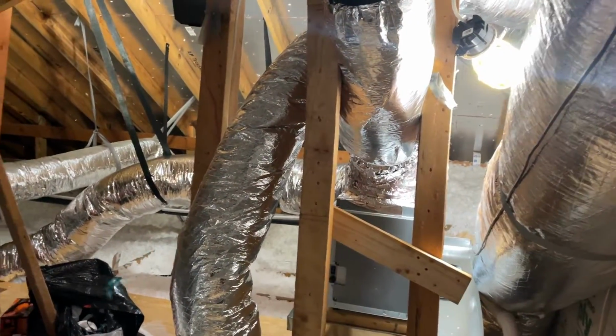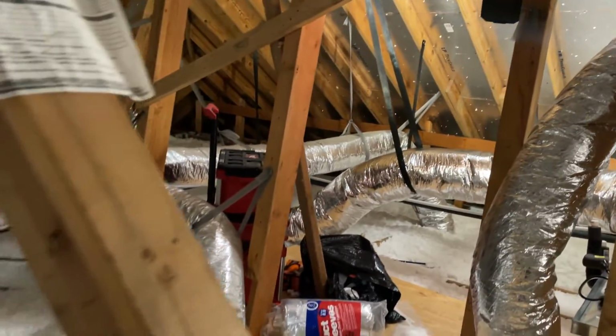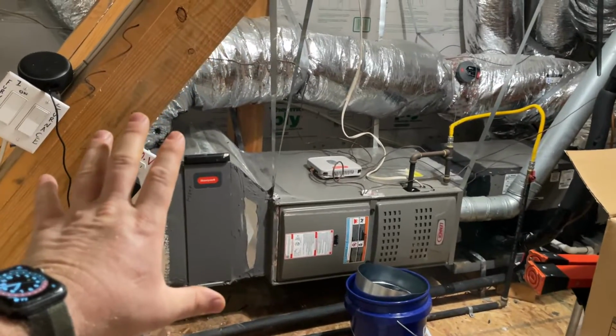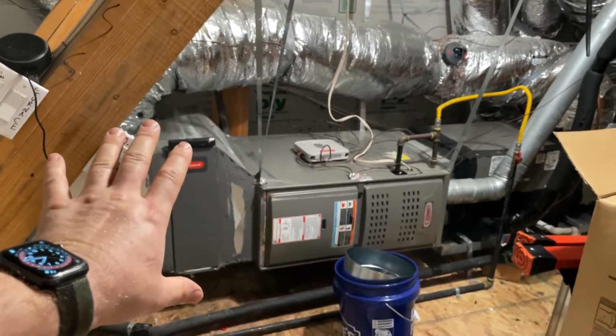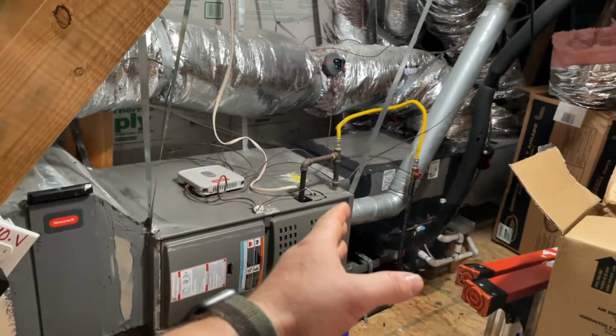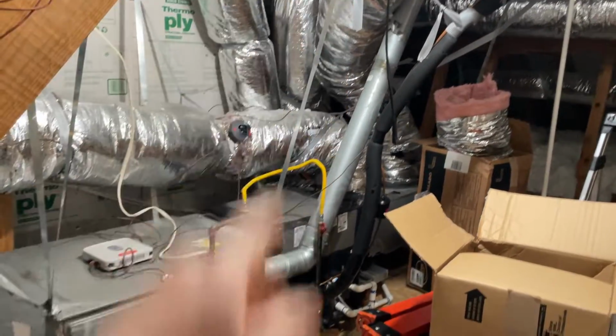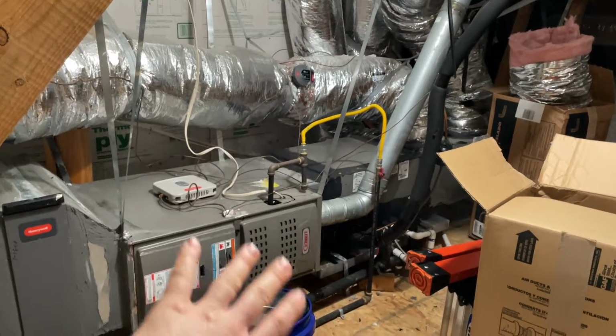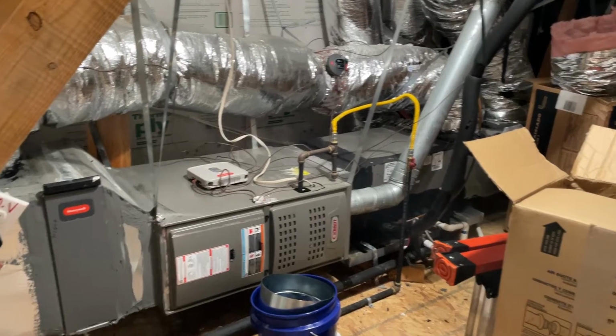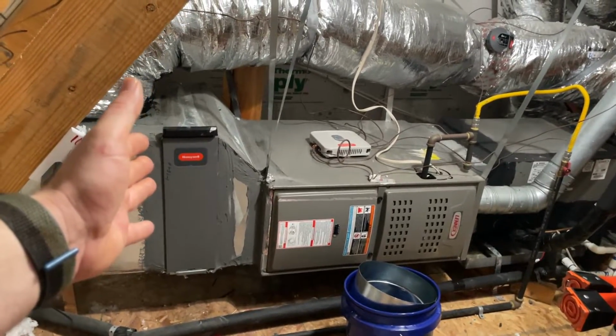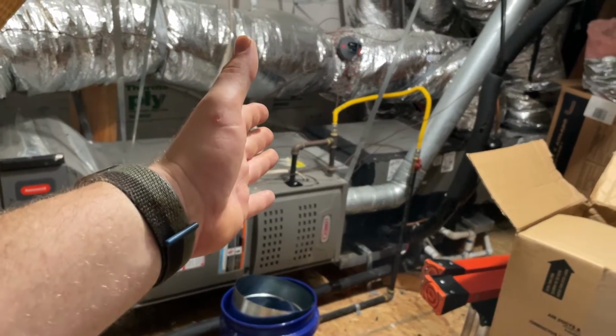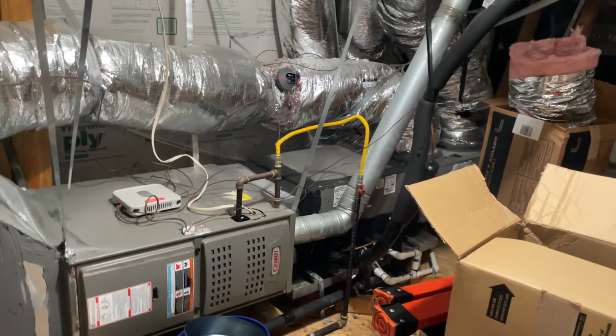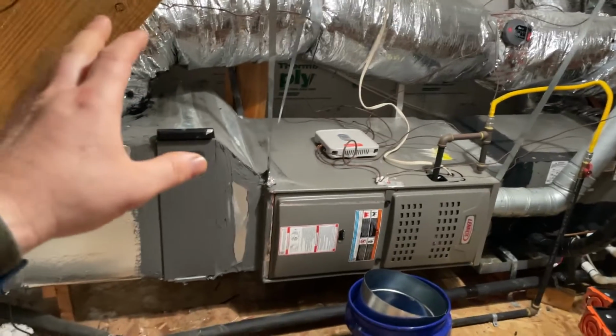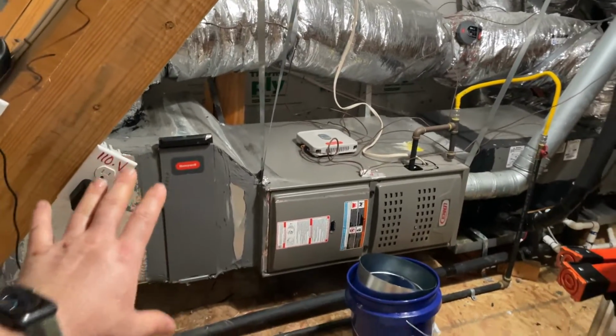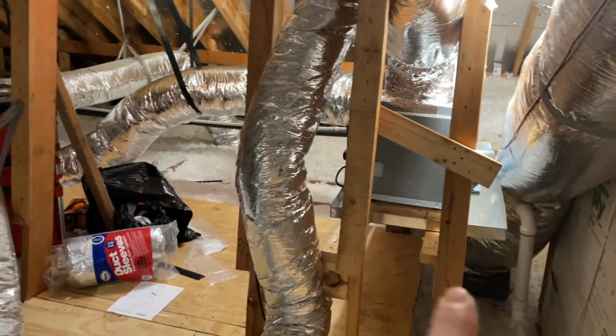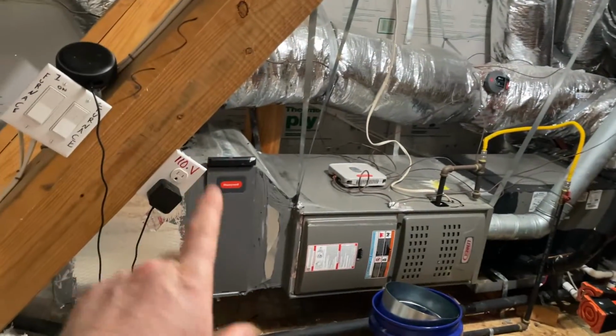The dehumidifier needs to supply dehumidified air. In a regular air conditioning setup, the return side is air coming in from the house, going through the compressors, getting cooled, and then supplied back to the house. There's a dehumidification and rehumidification process taking place, especially at the evaporator coils. If you feed it dry air, for practical purposes it just ends up rehumidifying and dehumidifying it again before sending it back out. So it doesn't make sense to put a dehumidifier on the return side of an AC system — the supply of the dehumidifier should not feed the return of your AC system.